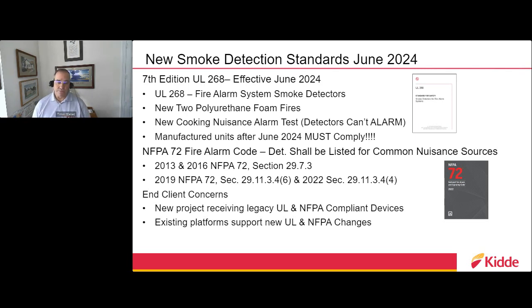This isn't just a UL requirement—there's also a code requirement around nuisance sources. The NFPA 72, the primary code standard that fire alarm systems follow, in the 2013, 2016, 2019, and new 2022 editions, all have requirements around this nuisance issue.